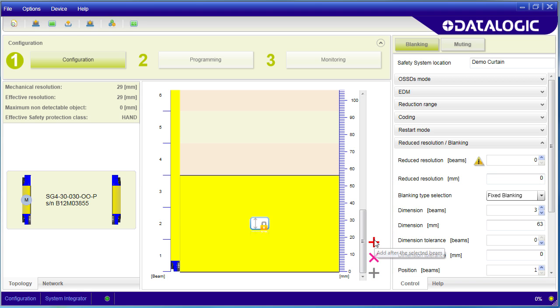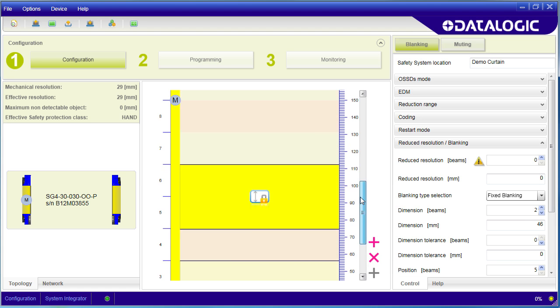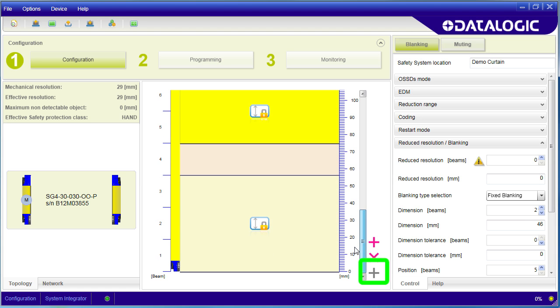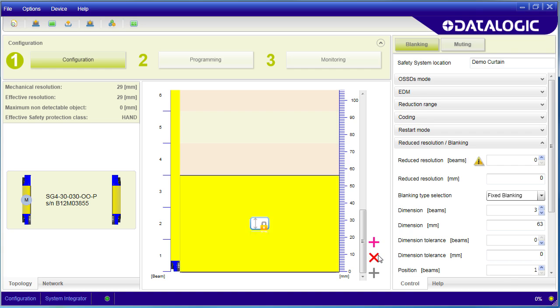To add another blanked out area above this area, click on this plus sign. To add one below, click on this plus sign. You can have up to five blanked areas on a light curtain. To delete a blanked area, just select it and hit the X.